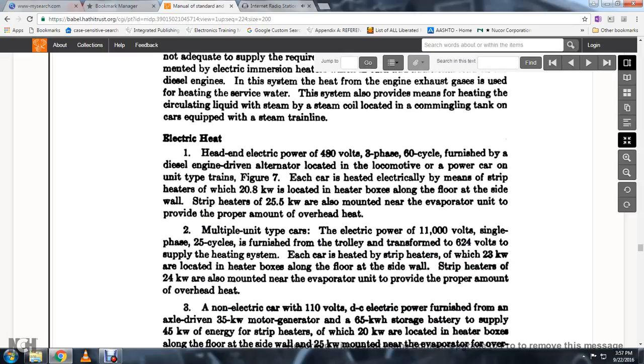Electrical heat. Head-end electrical heat power at 480 volts, 3-phase, 60-cycle, is furnished by the diesel engine alternator located in the locomotive power car on unit-type trains. In Figure 7, each car is heated by electrical strip heaters of which 20.8 kilowatts is located in the heater box along the floor at the side wall. Heated strip heaters of 25.5 kilowatts are mostly mounted near the evaporator unit to provide the proper amount of overhead heat. For multiple unit type cars, electrical power of 11,000 volts single phase, 25-cycle, is furnished via trolley transformer at 624 volts for the heating system. Each car is heated with strip heaters of 23 kilowatts located in the heater box along the floors and side wall, with 24 kilowatt strip heaters mounted near the evaporator unit for overhead heat.